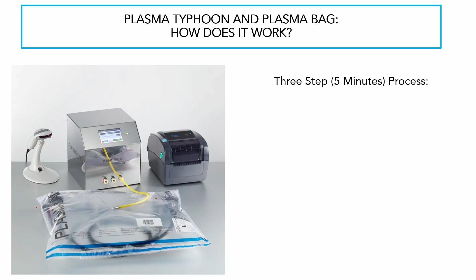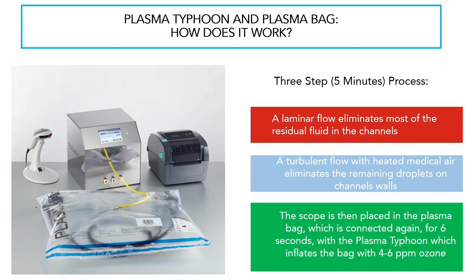The process is a very quick process, which involves 3 steps, which can be performed in less than 5 minutes. In the first one, a laminar flow eliminates most of the residual fluid in the channels. Then, a turbulent flow with heated medical air eliminates the remaining droplets on the channel walls. And at this point, the scope is put into the plasma bag, which is connected again for a few seconds with the plasma typhoon, which inflates the bag with ozone, which has antimicrobial properties.